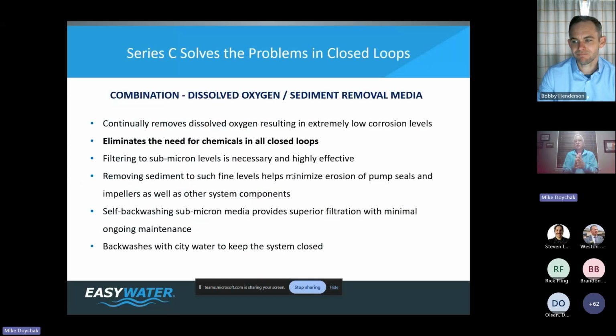So what are the two stages? Here they are. First stage is a combination of dissolved oxygen removal media and sediment removal media. What this is going to do is work to continually remove that dissolved oxygen, get it to a point where it's not in there and it's not corroding the metals inside. We again are going to eliminate the need for all chemicals. So we don't want the chemicals in there.